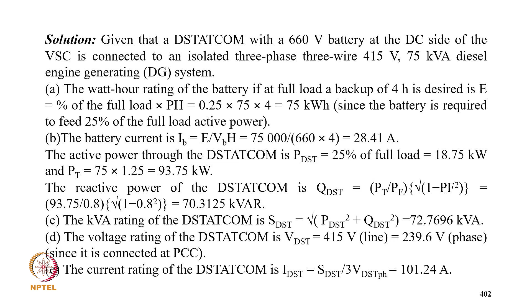The active power through the STATCOM is 25% of load, that's 18.75 kilowatt, and PT comes to 93.75 kilowatt. The reactive power of the STATCOM is QST equal to PT upon power factor squared, so it becomes 70.3125 kVAr. So the kVA rating of the STATCOM is the square root of PST squared plus QST squared, which is 72.769 kVA. The voltage rating of the STATCOM is 415 to 230, and the current rating is ST upon 3 VST, so it comes to 101.24 ampere.